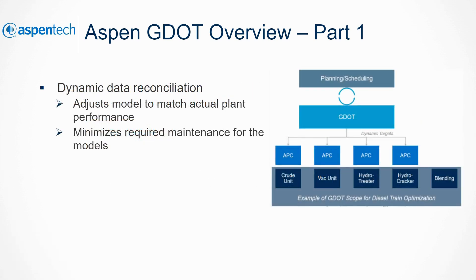GDOT has many unique features. GDOT uses a patented dynamic data reconciliation technology to adjust models to match actual plant performance. The data reconciliation makes the models very low maintenance, since they will be automatically recalibrating. The data reconciliation also allows for updating parameters in planning models. Since GDOT is constantly updating with data of the actual performance of the plant, new values of constraints on plant performance can be sent to the planning model, improving its performance. This enables planners to make more aggressive and accurate plans, pushing the plant to its optimal performance.